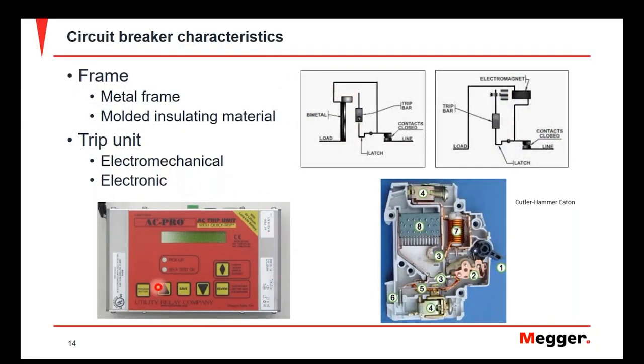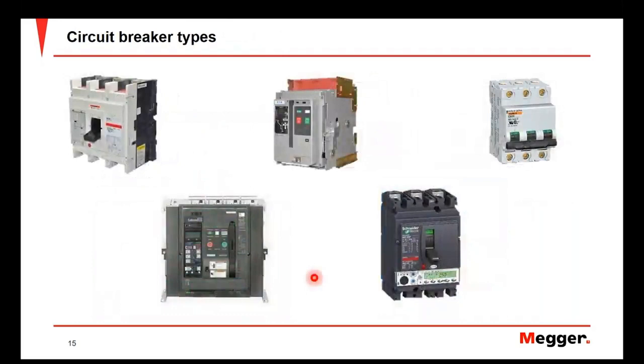For electronic trip units, a set of current sensors is mounted to the main conductors of the circuit breaker. They send signals to the electronic trip unit, which then outputs to a trip mechanism to open the breaker. Examples shown include molded case circuit breakers outfitted with electronic trip units, metal frame breakers also with electronic trip units, and a miniature breaker that you may see in a control power scheme.